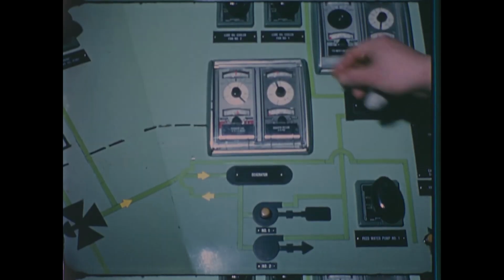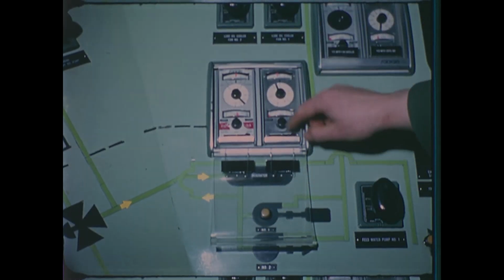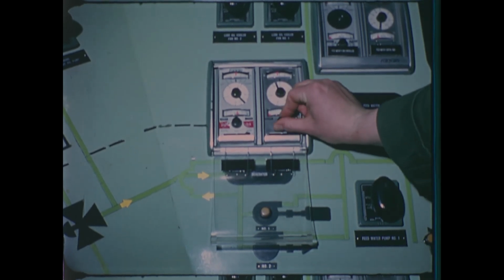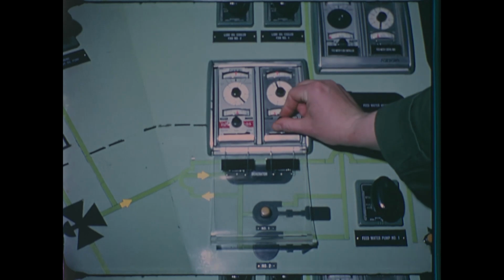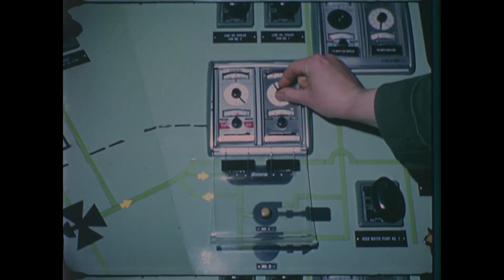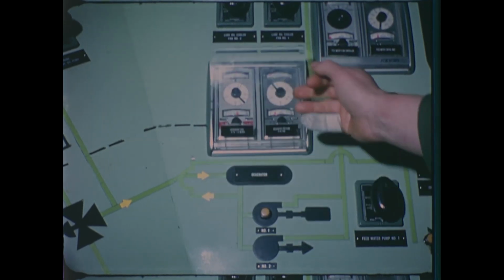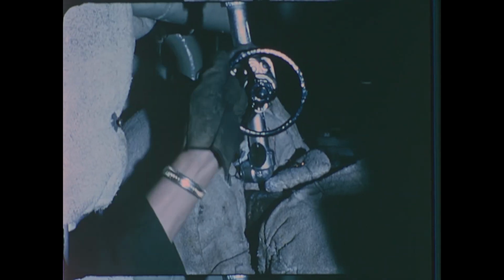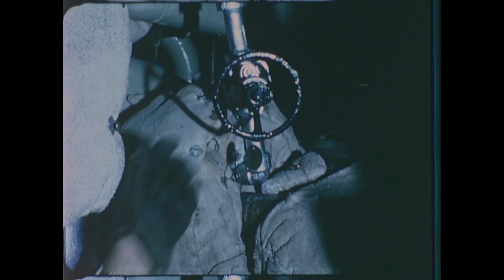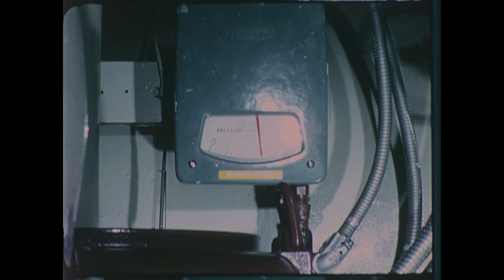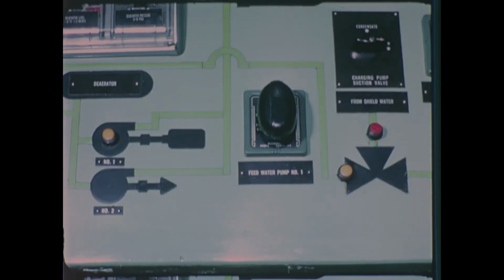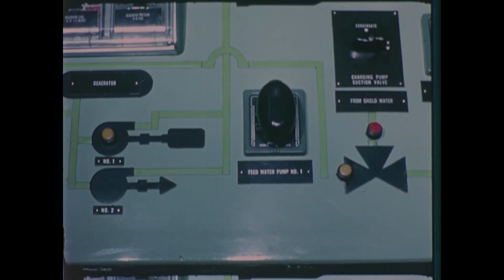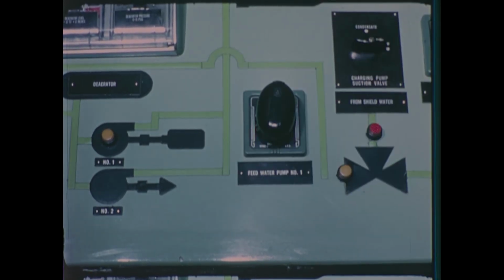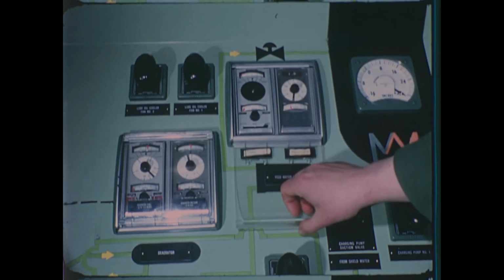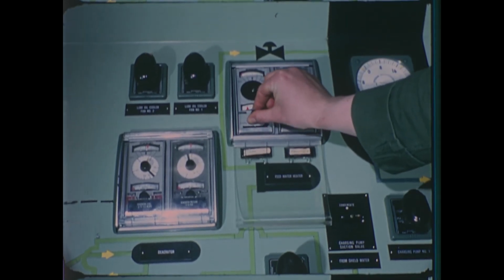The console operator will establish the deaerator pressure by operating the deaerator pressure controller remotely. Open the deaerator vent to discharge non-condensable gases to the atmosphere. Now the deaerator pressure controller may be switched to automatic. The steam generator level is maintained by starting the feedwater pump from the console. Now the console operator fills the steam generator by manually controlling the feedwater flow controller slowly.